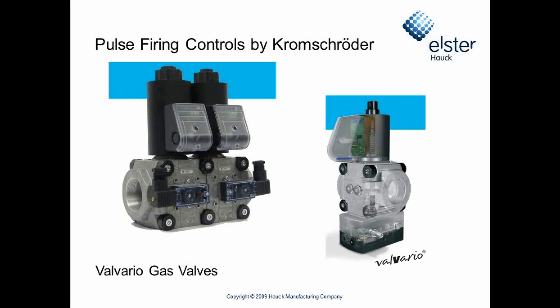The Kromschroder solenoid valves, again, are specifically designed for pulse fire applications, the high duty cycle. Kromschroder solenoid valves have a minimum duty cycle of 10 million cycles. They have integrated flow control built in, and on the right side of the screen you will see a combination ratio regulator solenoid valve. The nice thing about the Kromschroder valves is they can also be installed in the vertical orientation, allowing you to minimize your piping footprint.